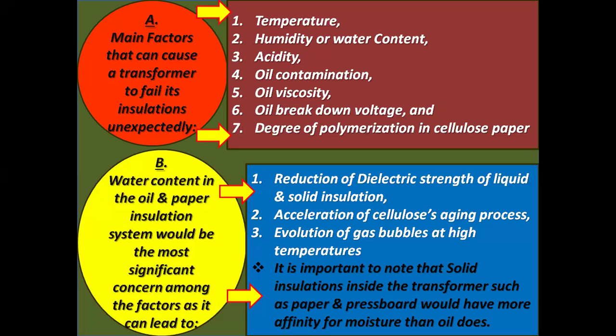Now see the main factors that can cause a transformer to fail its insulation unexpectedly. One: temperature, humidity or water content, acidity, oil contamination, oil viscosity, oil breakdown voltage, and degree of polymerization in cellulose paper. Two: water content in the oil and paper insulation system is the most significant concern among these factors, as it can lead to reduction of dielectric strength of the liquid and solid insulation, acceleration of cellulose's aging process, and evolution of gas bubbles at high temperatures.